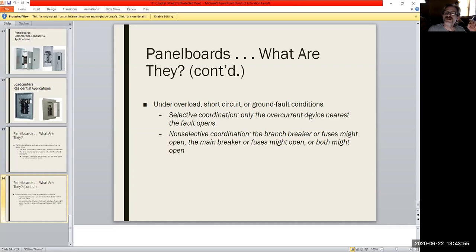Because when you get down to it, you're limited by what the weakest link is in your product. So whatever the overcurrent devices are, that's what it falls back on. That's your extreme limitation. It's like, okay, I can't pull any more current than this, because this is my limiting factor. And everything else is sized accordingly with that.